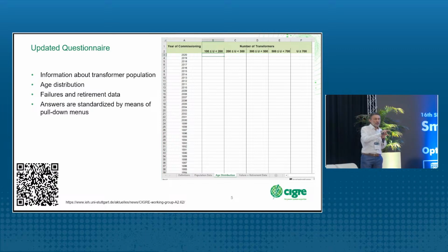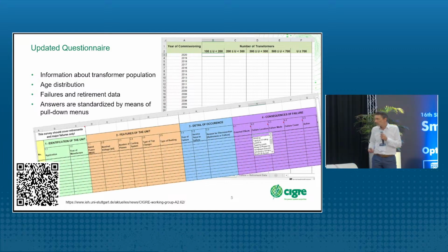First, you also need information about the living population of the transformers. If you want to assess the failure rate, of course you have to know how many transformers are operating in the network, and also how old these transformers are. So the operators had to fill in such an Excel sheet where they had to write down how many transformers they commissioned in each year in different voltage classes. From this we got the age distribution of the transformer population of the respective utility. Then of course we collected the data about the failure itself.